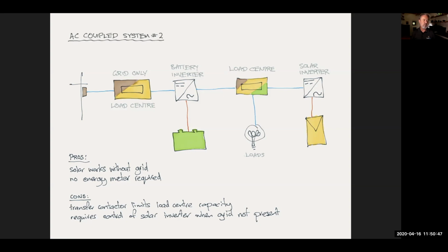And it does require, and this is generally proprietary, some way of controlling the solar inverters when the grid is not present. What I mean there is, if the grid fails and you are charging from a solar inverter via your battery inverter, your battery system, what happens when that battery's full? How does the solar inverter know to stop pushing power out towards the loads? That's where communication comes in, and it can be done with frequency, or it can be done with a data cable, but the battery inverter needs to tell that solar inverter when to ramp back. Right.